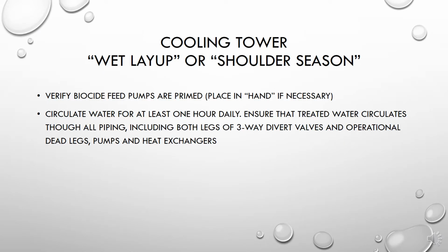So like I said, we have that wet layup or shoulder season where we want to prevent the equipment from sitting idle, and we want to prevent water age, basically. So you want to verify that your biocide feed pumps are primed. You can place them in hand via the controller if necessary to make sure that they're primed. And we want to circulate water for at least 1 hour every day, and this ensures that the treated water circulates throughout the entire system and picks up that chemical. And you want to make sure that you are circulating it through all of your piping, heat exchangers, operational dead legs, pumps, and if you have a 3-way divert valve, you want to make sure that you are including both legs of that.